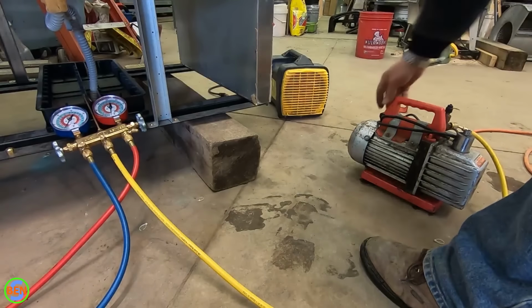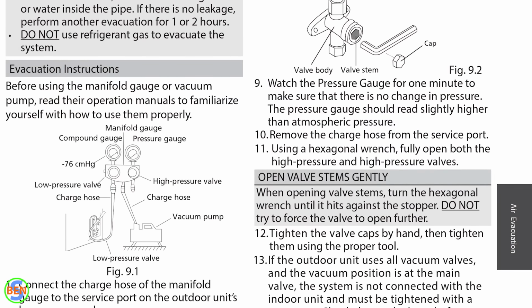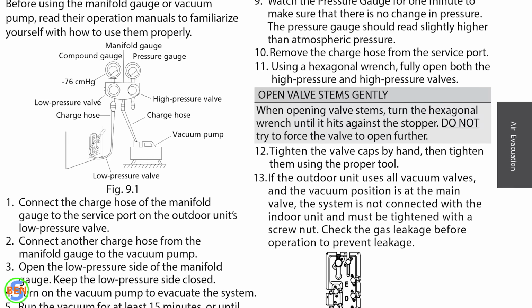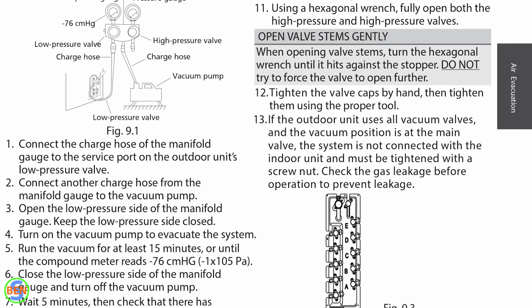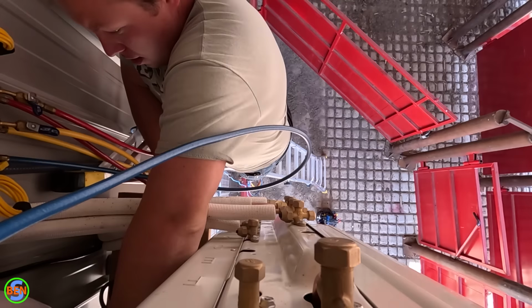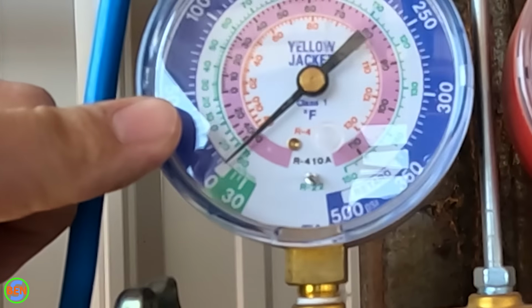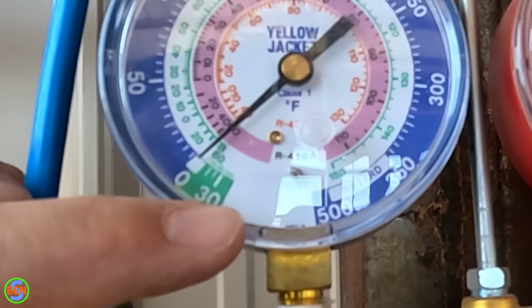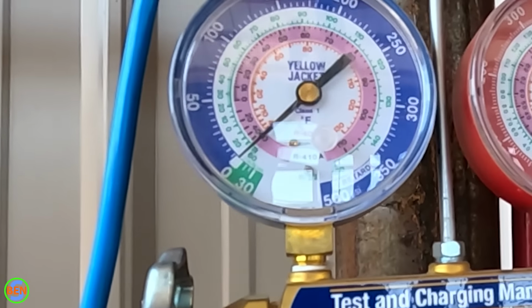And this is probably the most frustrating part of the process for me sometimes. Pulling a vacuum can be really finicky, and it seems like you can never really achieve that perfect 500 microns like the manufacturers often suggest. Now the interesting thing is it doesn't actually talk a lot in the manual about the exact number of microns that they want. I did talk to Cooper and Hunter, and they did say 500 microns just like all the other manufacturers. But what I generally find is that getting it to 500 microns can be really tricky, and a lot of times you don't even know if you're there or not. If you're using a regular set of gauges, you're only going to be able to see that needle down in a vacuum, and you're not going to be able to see how many microns it is anyway.